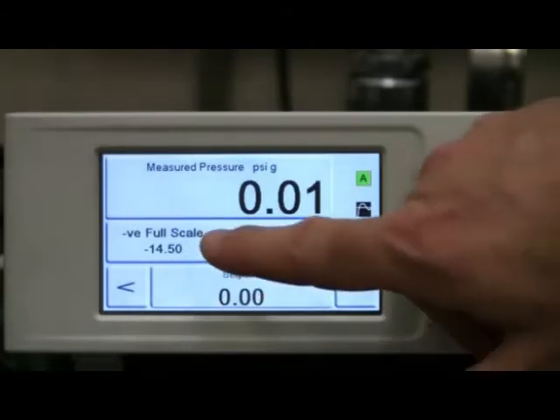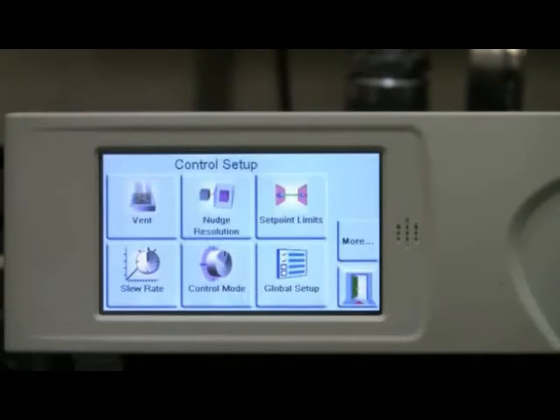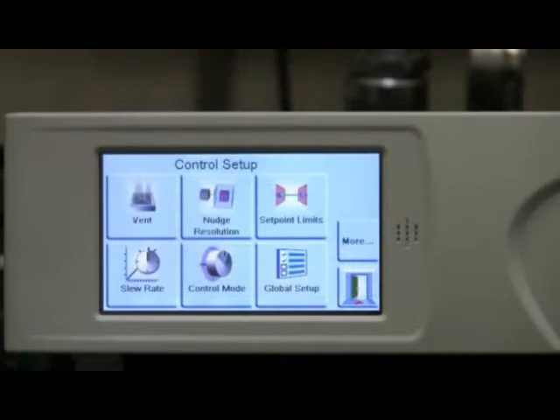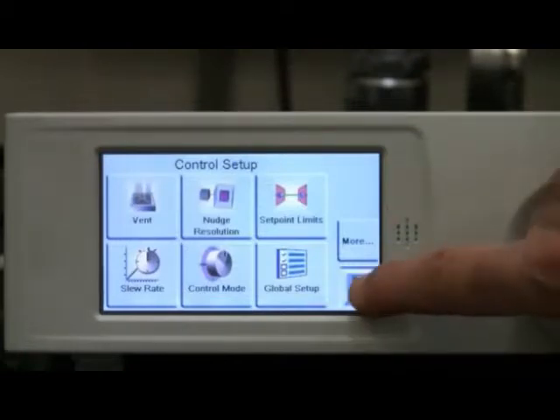The center section is the Control Setup menu. Here, we can vent the test port to atmosphere, select the nudge resolution, change the high and low set point limits which help protect the device under test, select the Control Speed parameters, and also access the Global Setup menu.